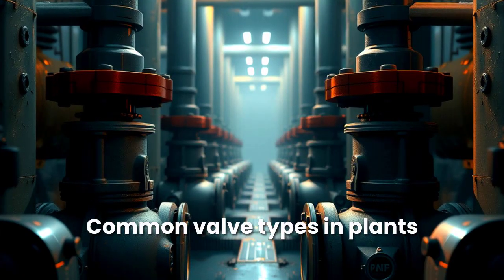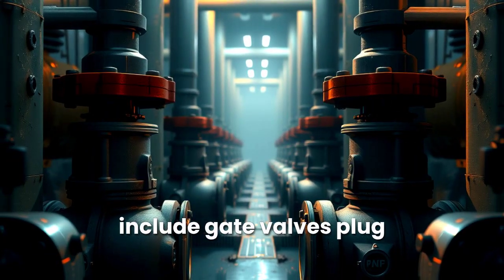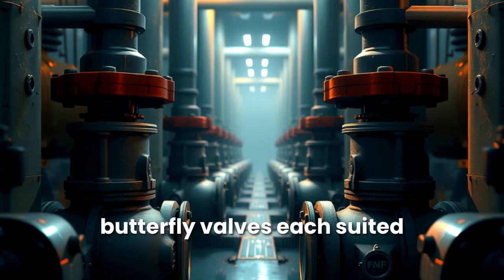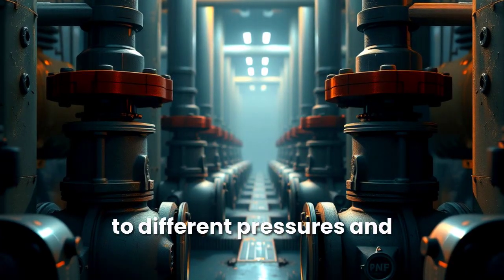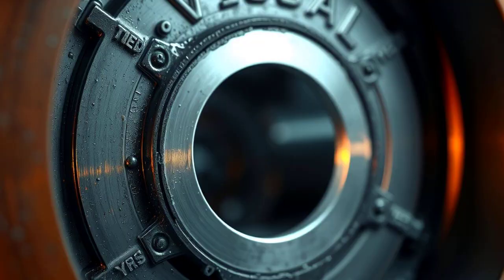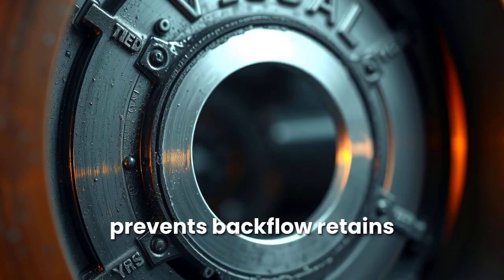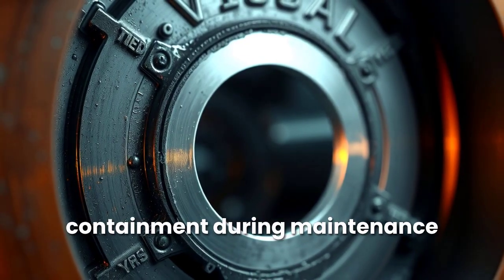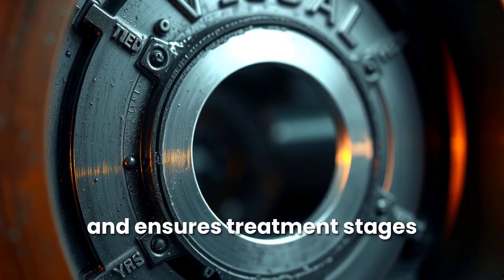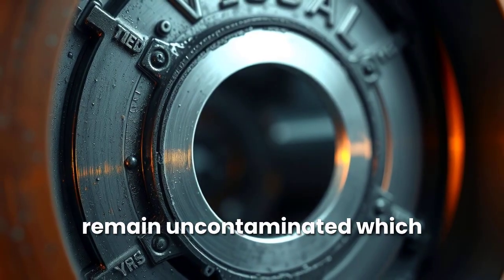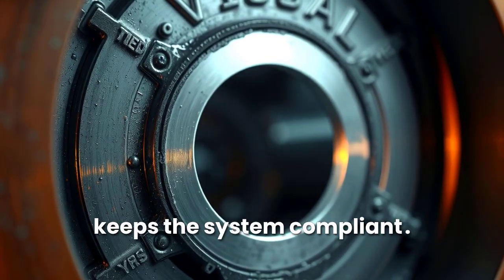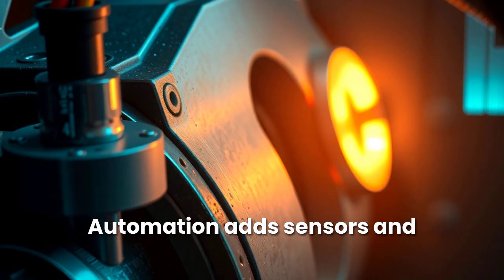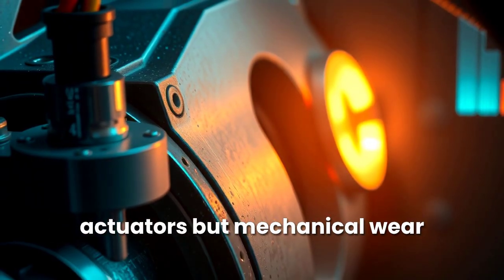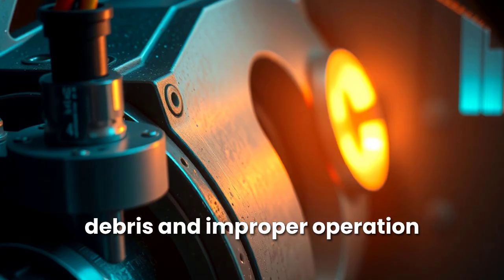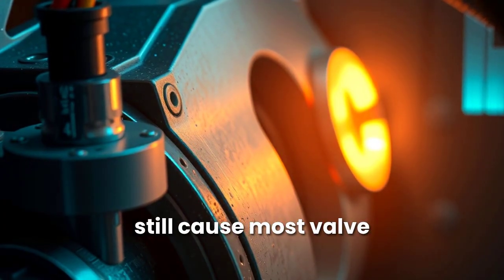Common valve types in plants include gate valves, plug valves, ball valves, and butterfly valves, each suited to different pressures and services. A properly seated valve prevents backflow, retains containment during maintenance, and ensures treatment stages remain uncontaminated, which keeps the system compliant. Automation adds sensors and actuators, but mechanical debris and improper operation still cause most valve failures despite electronics.